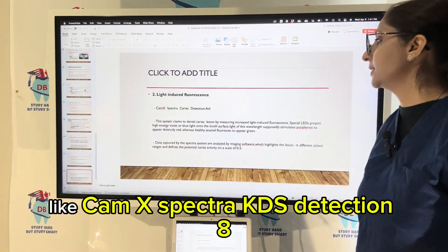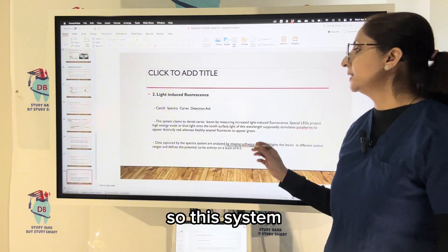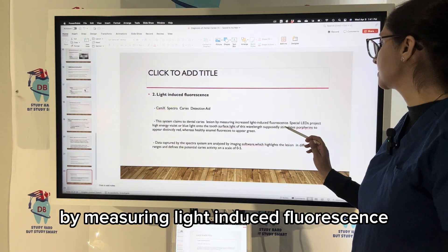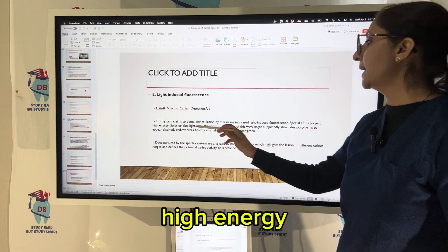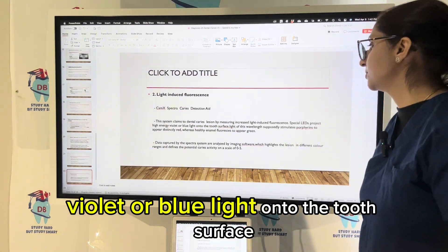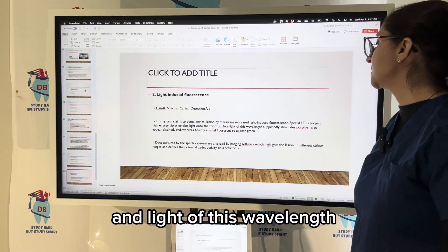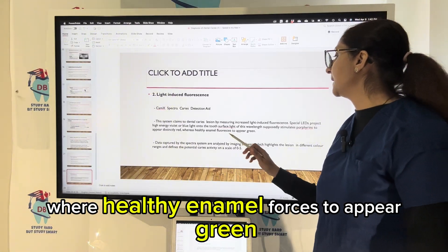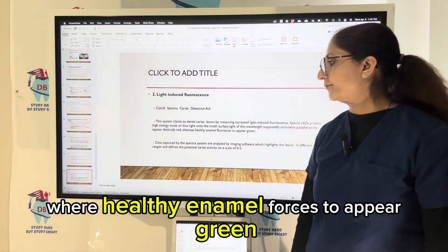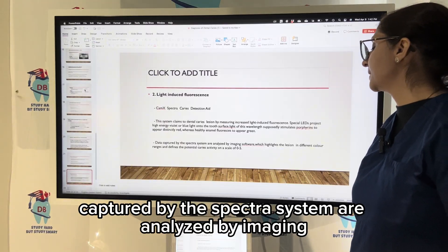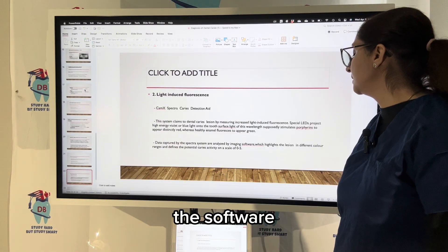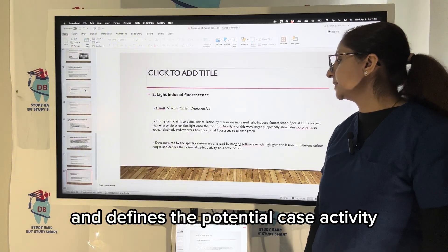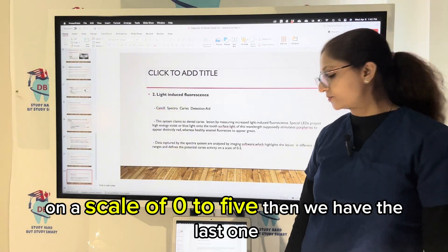Another method is light-induced fluorescence, such as CamX Spectra caries detection aid. This system detects the caries region by measuring light-induced fluorescence. A specialized LED projects high-energy violet or blue light onto the tooth surface, which stimulates porphyrins to appear distinctly red, while healthy enamel fluoresces green. Data captured by the spectral system are analyzed by imaging software, which highlights lesions in different color ranges and defines potential caries activity on a scale of 0 to 5.